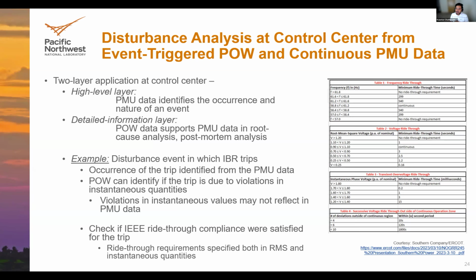Another important feature that can be utilized is that you can do ride-through compliance testing for this. All these IBRs have mandates on what their ride-through performance should be. These are specified for both voltage and frequency, and voltage both in terms of RMS quantities as well as instantaneous quantities. So you can check whether a trip like the one that I showed was a legitimate trip because of the voltage and currents being outside the permissible limits of ride-through, or was it something that was not allowed and the IBR tripped anyway, which can be used for flagging nuisance trips. All this analysis can be performed if we have the high-resolution point-on-wave data at our disposal.